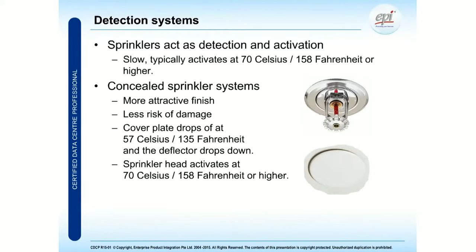This is a slow system because generally these systems are only triggered when the ambient temperature around the nozzle reaches 70 degrees Celsius or more. At that point the sprinkler starts blowing out water, and that's quite a lot of water. We also have concealed systems, shown at the bottom, which pop out of your concealed ceiling at an ambient temperature of about 57 degrees Celsius, and only start releasing water once the ambient temperature reaches 70 degrees Celsius.